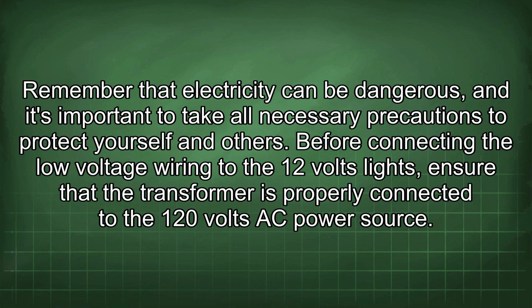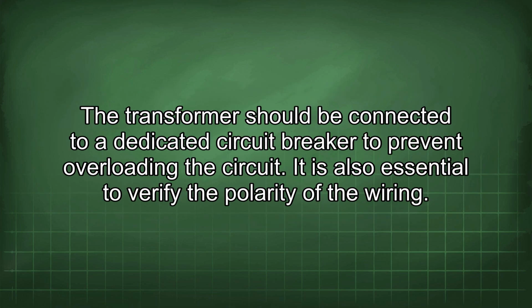Before connecting the low voltage wiring to the 12 volts lights, ensure that the transformer is properly connected to the 120 volts AC power source. The transformer should be connected to a dedicated circuit breaker to prevent overloading the circuit.